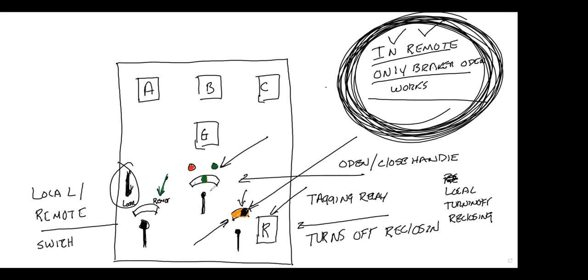Whoever did it is going to get a call back from the dispatcher: SCADA's back up, but you put that breaker in open. I need you to go back and put it to the closed position, or red, before I can close it by SCADA. That's another safety feature. So SCADA really can't take over what you have done. Got it. But you're not really closed until that recloser closes, correct? Opening and closing the breaker by handle does not have anything to do with reclosing. Got it.